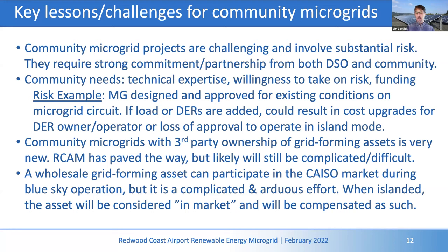If there's load added to what's part of the islanded circuit, or what can be the islanded circuit, we may need to redo the microgrid islanding study and make sure that can be done safely and reliably. And if there need to be upgrades, whether to the DERs or other aspects of the system, those would fall on the community microgrid aggregator. If the community decided they couldn't or weren't willing to handle that added cost, they may lose the approval to operate in island mode because it couldn't be done safely or reliably.